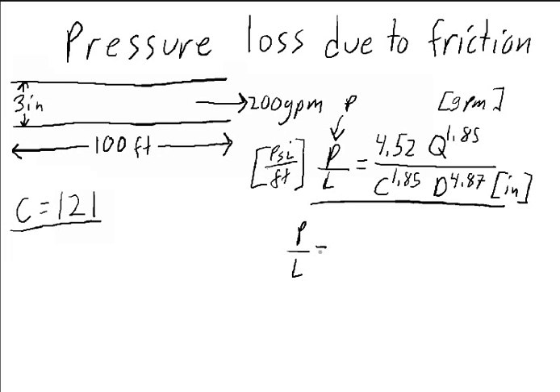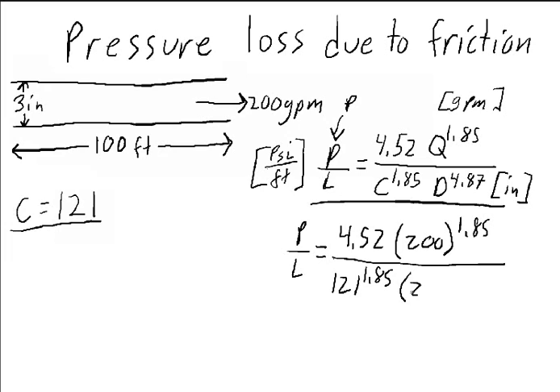It's equal to 4.52 times our flow rate, 200, raised to the 1.85 power, divided by 121 raised to the 1.85 power times 3 to the 4.87 power. We have a 3 inch pipe.